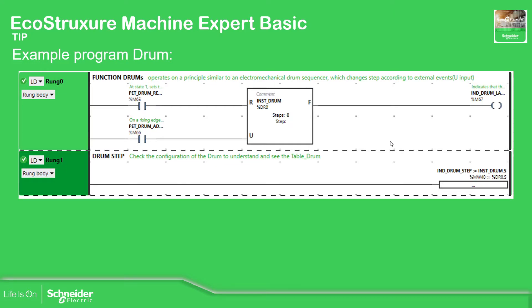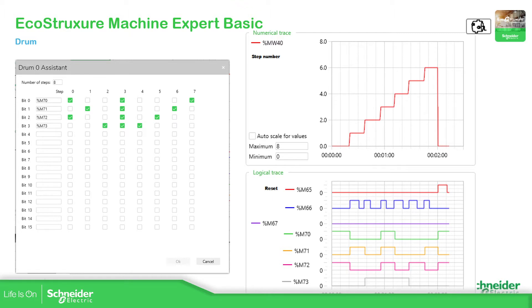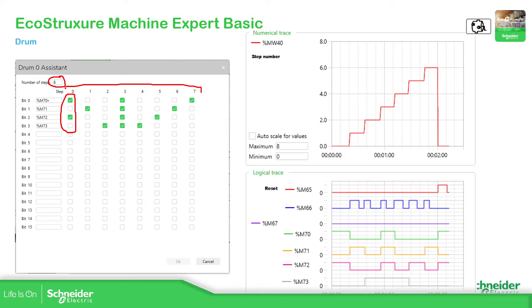Here is an example of how you can use the drum. I created two variables at the input, one at the output, and a variable to show the actual step of the drum in a %MW variable. When you open the drum configurator, you can specify the number of steps. Depending on the step you are on, you can activate some bits using %N or %Q.